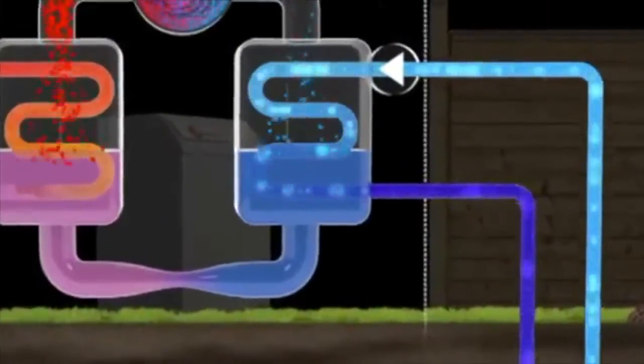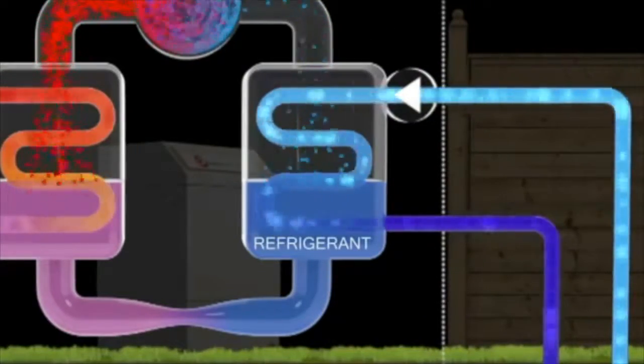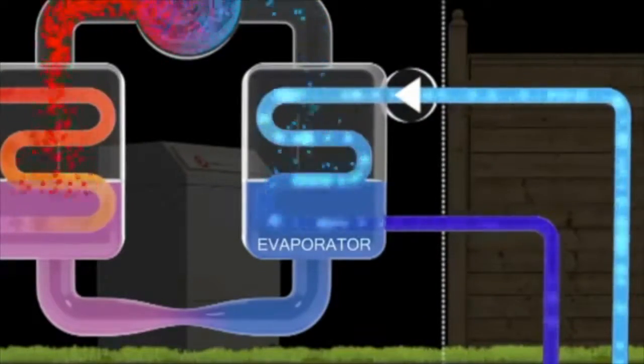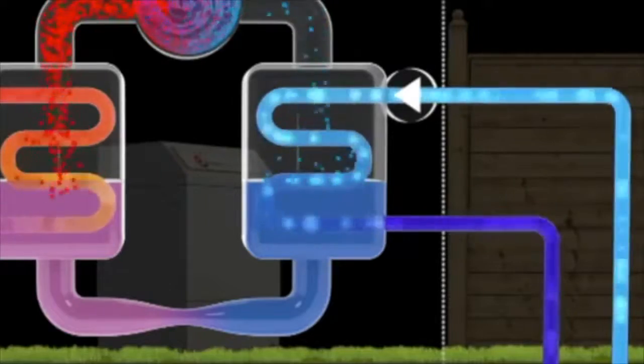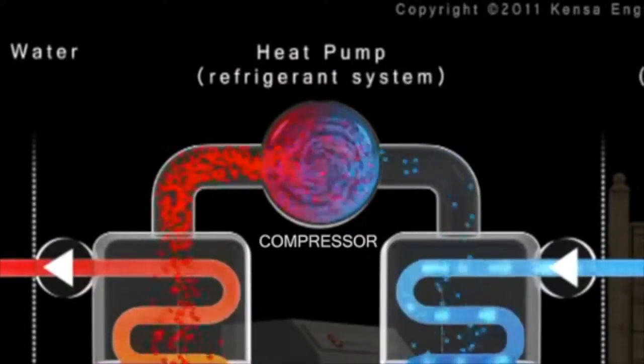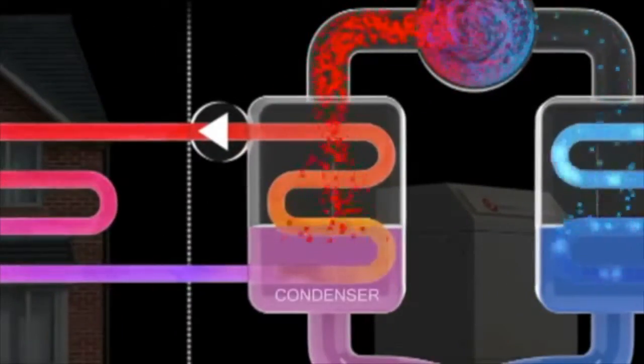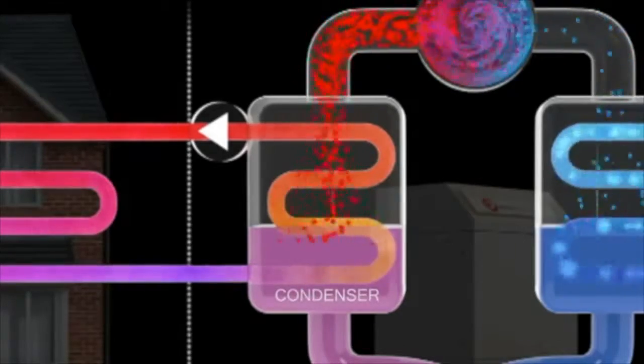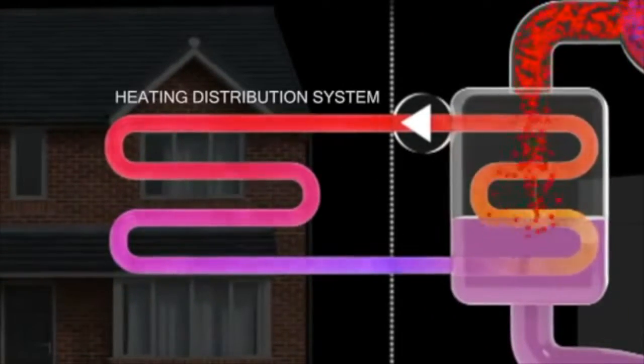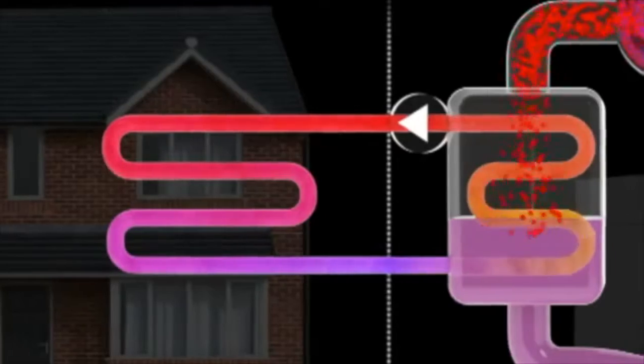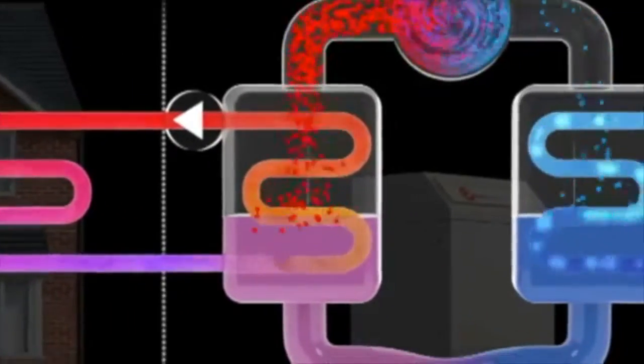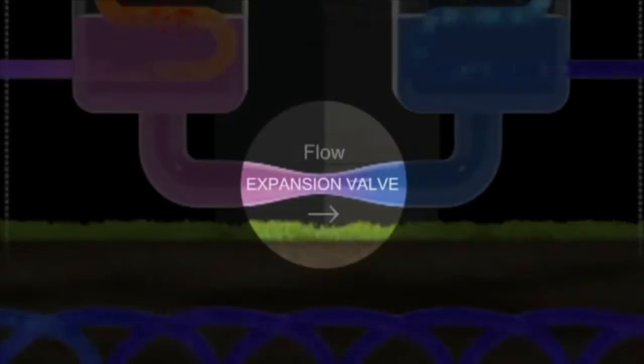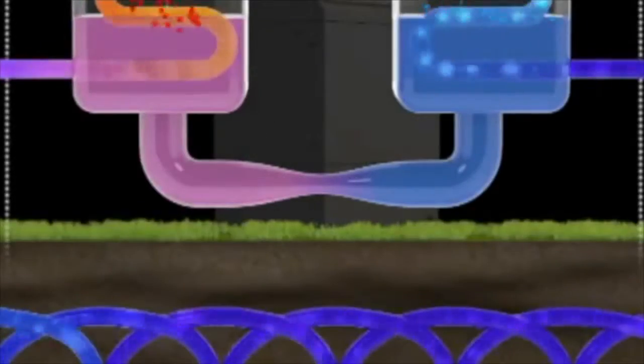The heated mixture provides thermal energy to a refrigerant in a plate heat exchanger, which then begins to boil. The refrigerant gas is then compressed to a superheated state and transfers its heat to water through a condenser, which will then be used as a heating source for space heating and hot water supply. As the refrigerant transfers its heat, it condenses and passes through an expansion valve, which lowers its pressure and temperature before it is recycled again.